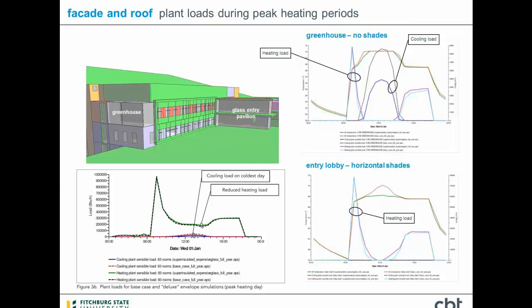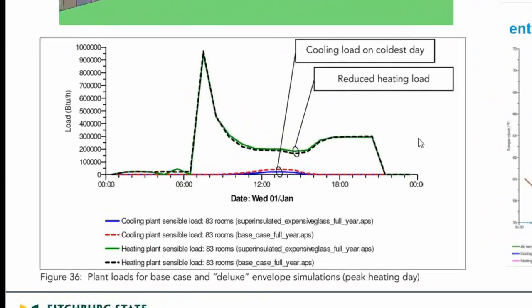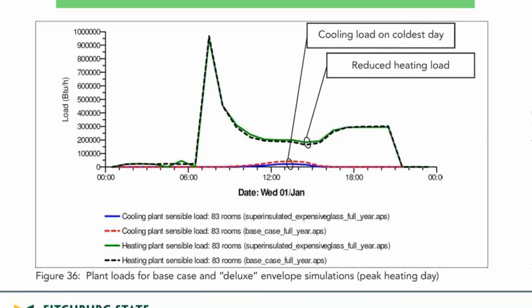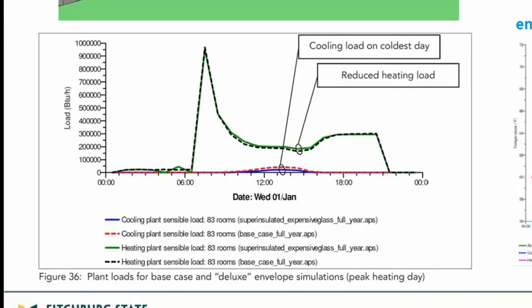When we looked at the overall building performance for more global issues, IES, as part of that process, we were able to look at all the data aggregated into one graphic, like we have down on the lower left here, which looks at overall building performance, but within the same files, we can actually go in and look at individual spaces. And I happened to be looking at the overall building performance on the peak heating day, and noticed that there was actually some cooling demand at midday in this building. I was curious as to where that might be so we can address that situation.